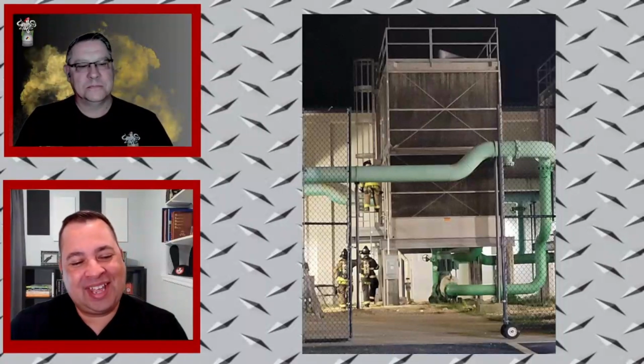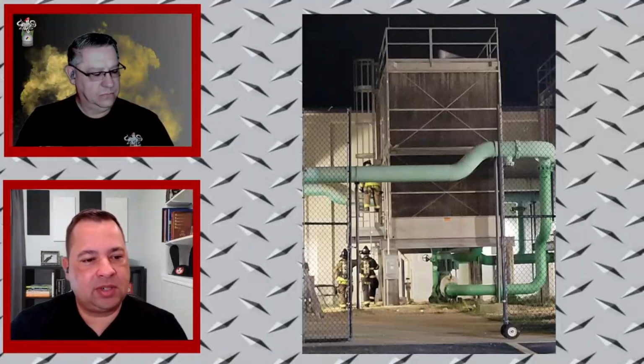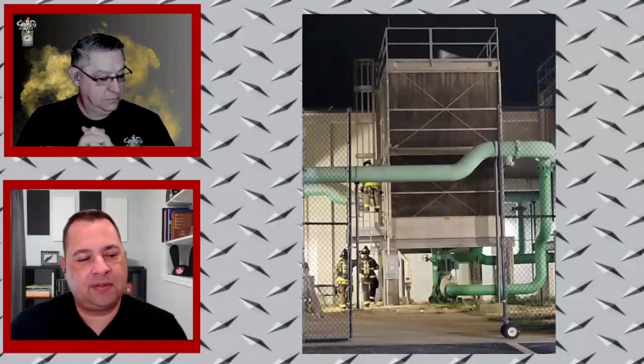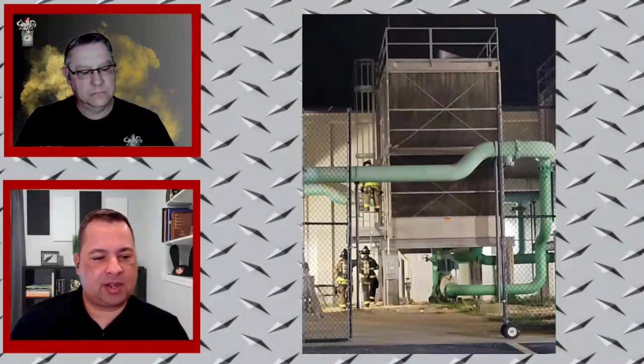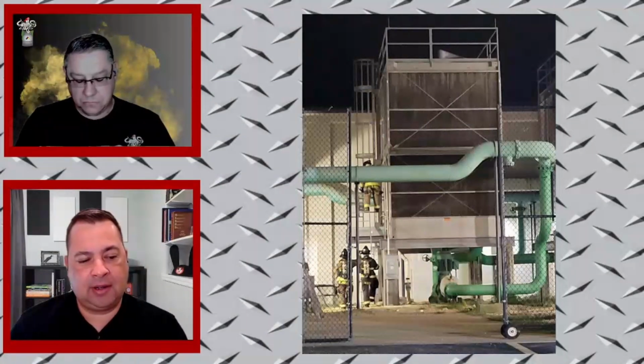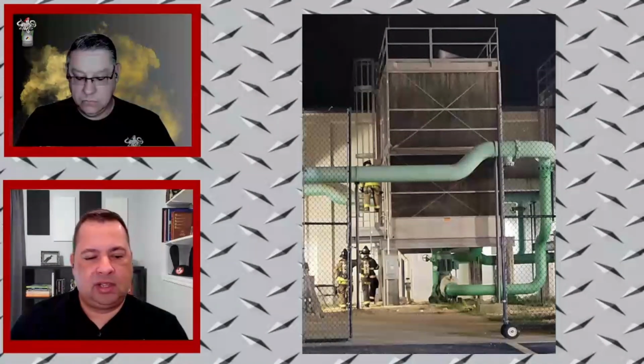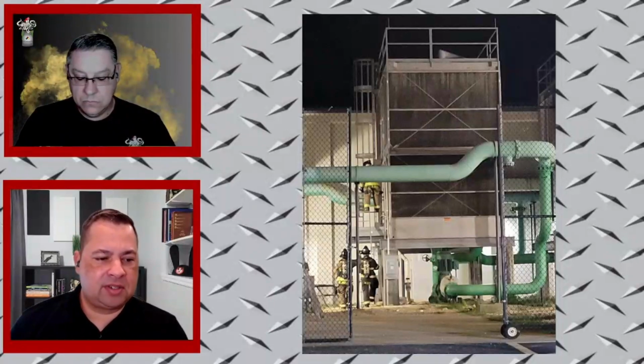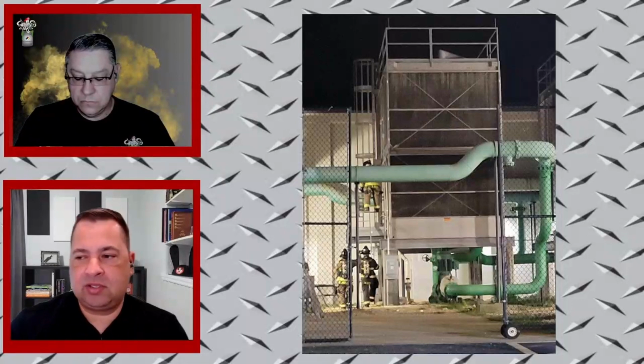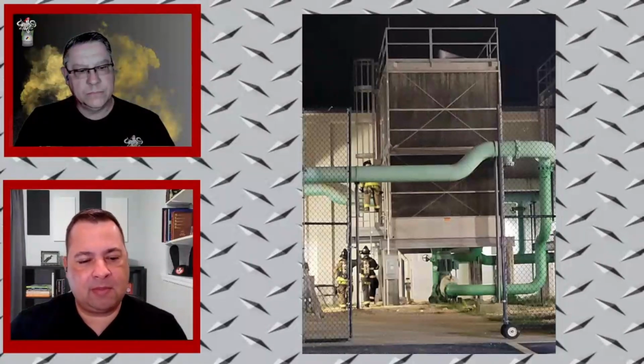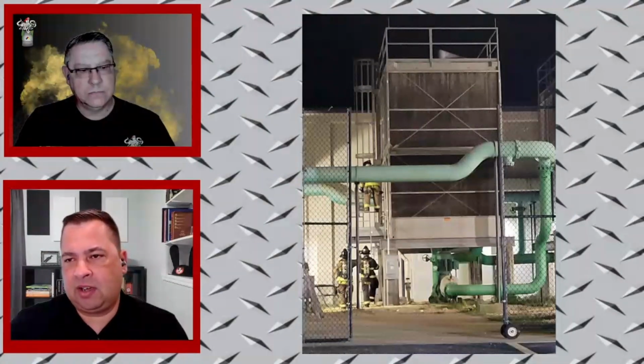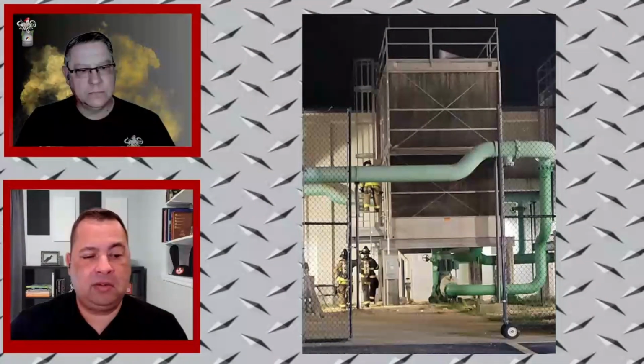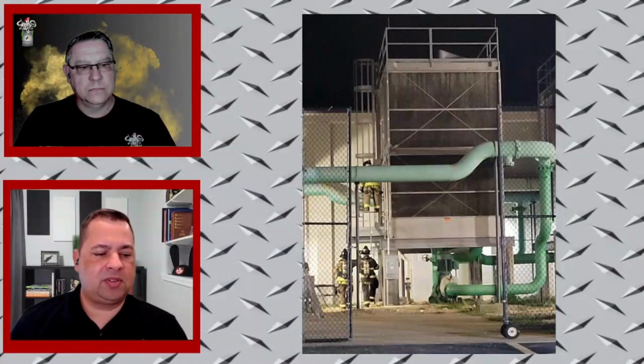So it's basically a descaling type solution, something to break things down. It's got a collection of different acids and sodium hydroxide in it - all things that can affect your electrochemical sensors to some extent. It also reacts with metals to release hydrogen, which could be an indicator to consider, since if it's being used to descale the system, it's coming into contact with certain metals. Is that a hydrogen concern being released? Maybe not enough to show on our combustible gas indicator, but enough to skew our CO or electrochemical sensors a little bit.